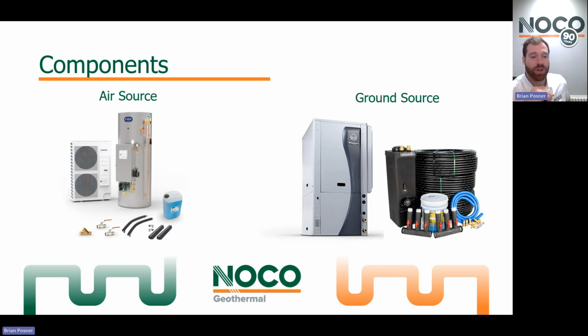It's usually going to be above the snow a little bit to try and limit how much it's going to be covered in snow or ice during the heating season. But that's your general equipment. You get your outdoor unit that's above the ground. With a ground source heat pump, you have high density polyethylene piping that's under the frost line. So again, we're capitalizing on that temperature in the Earth's crust that's a pretty constant 50 some degrees year round rather than that outdoor fan unit.